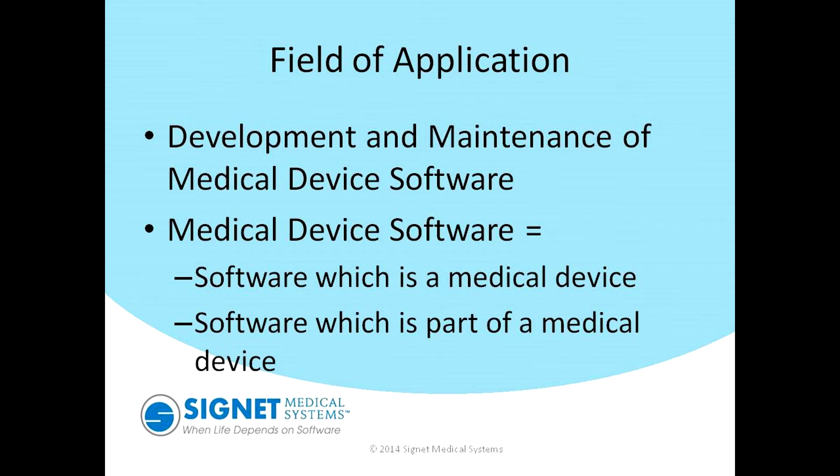The field of application for 62304 is specifically around medical device software — that's software within a medical device and software that is a medical device itself. I prepared a very large slide deck, but I know we don't have a lot of time. I want to get you to understand what is really the key to 62304, and you will receive this entire slide deck, which I think is very key to understanding the standard.